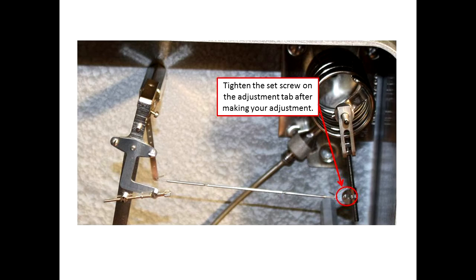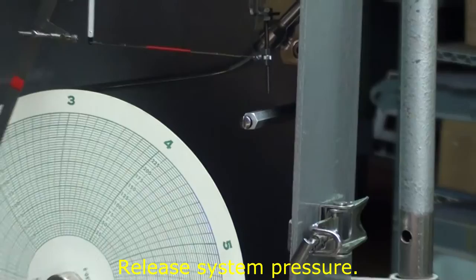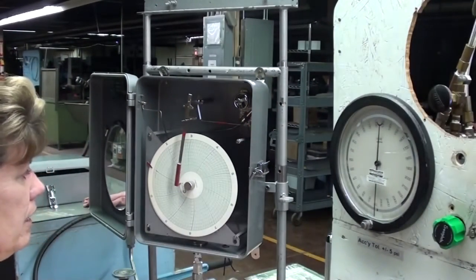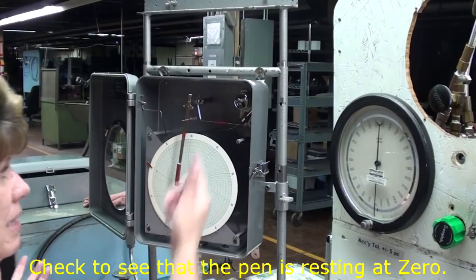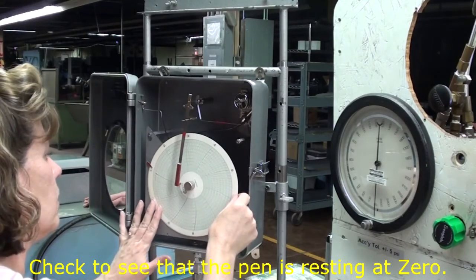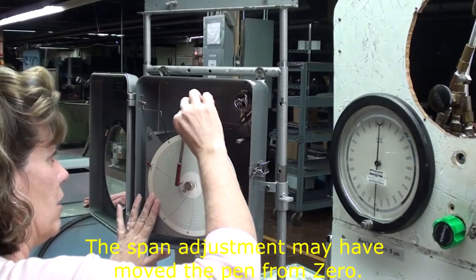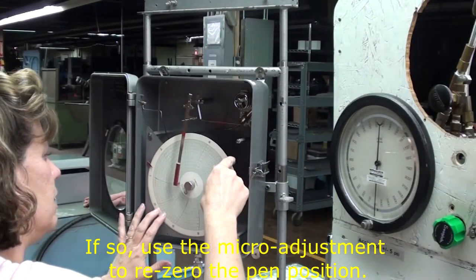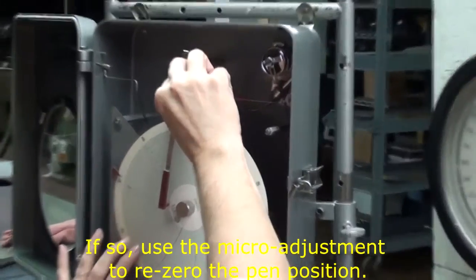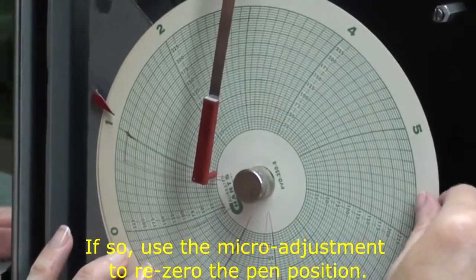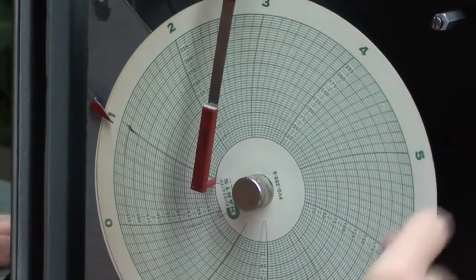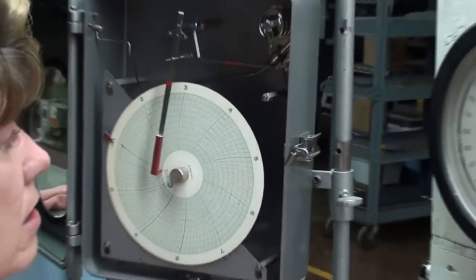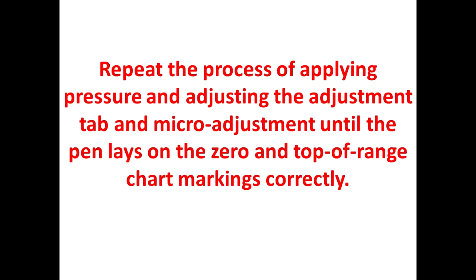So I take and release all my pressure. And as you can see, I'm no longer on zero, because I made an adjustment up here. So then I take my micro-adjustment, and I adjust my span back up to zero, because I am now at zero. So now we will simply repeat the process until we get the system calibrated.